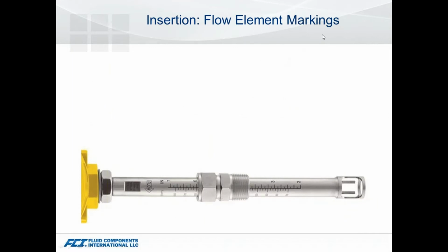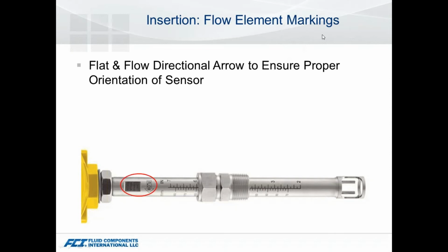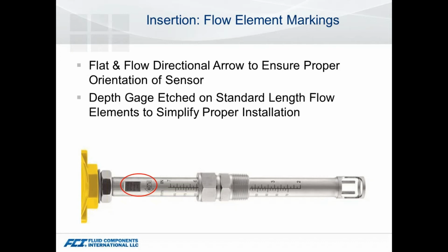On the elements itself, a few key features. You've got a directional arrow to show the orientation of it. That way our sensors are perpendicular to the flow, and we're installed in a way that the flow is matching the way it went into the stand at our factory. We mass balance those flow sensors, but you still are looking at some minor differences if that flow direction is reversed. Doesn't mean it's not going to give you a good reading. It just might introduce a small amount of inaccuracy. The next part to help simplify installation is a depth gauge.